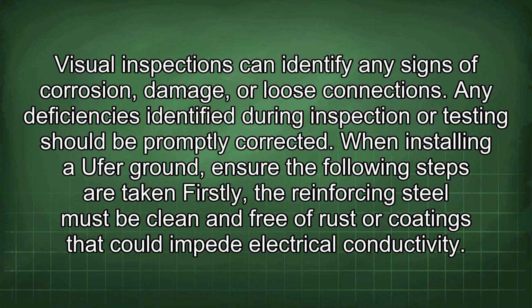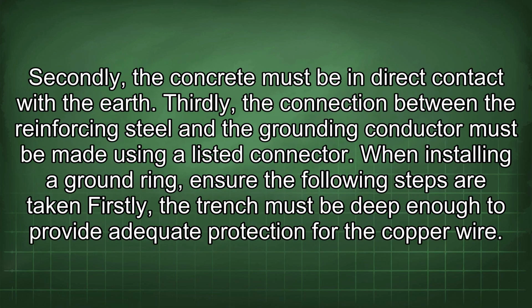Firstly, the reinforcing steel must be clean and free of rust or coatings that could impede electrical conductivity. Secondly, the concrete must be in direct contact with the earth. Thirdly, the connection between the reinforcing steel and the grounding conductor must be made using a listed connector.